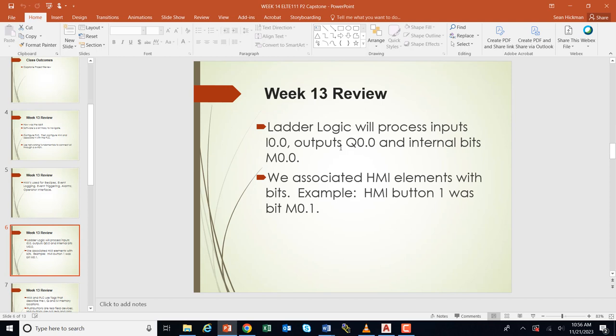Ladder logic will process inputs — that's what we learned. We take inputs I0, I1, I2, I3, which are real push buttons, switches, and everything like that. It solves ladder logic and pushes out outputs Q0, Q1, Q2, Q3, where we have real solenoids, real lights, and so on hooked up. We use internal bits to replace memory — to do memory, to replace control relays. We don't really need control relays for memory anymore. We can do it fictionally, and that's like M0, M1, M2, etc. We put the HMI elements in with bits because an HMI button doesn't really exist — a push button really does exist, but an HMI button is kind of fictional. We associate it with a bit and then write some ladder logic.